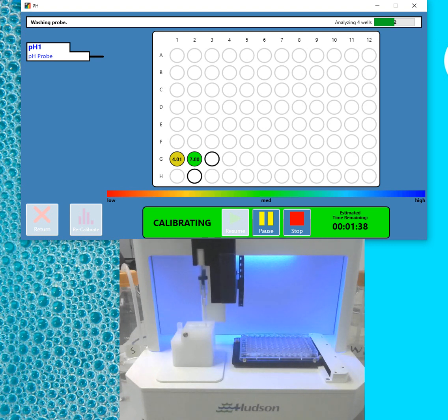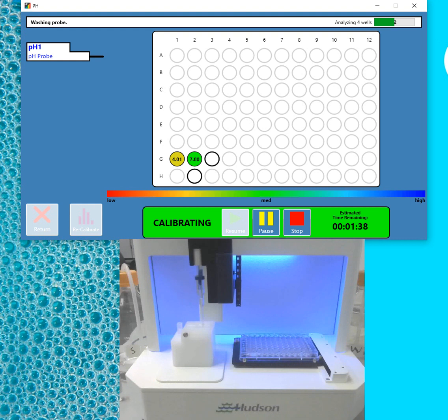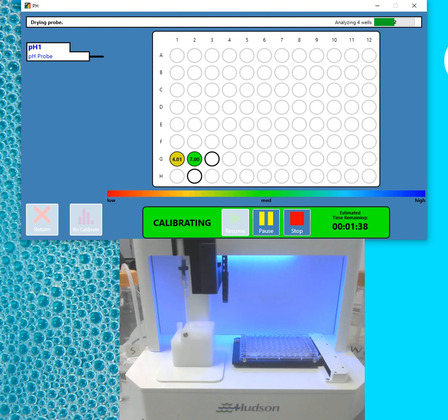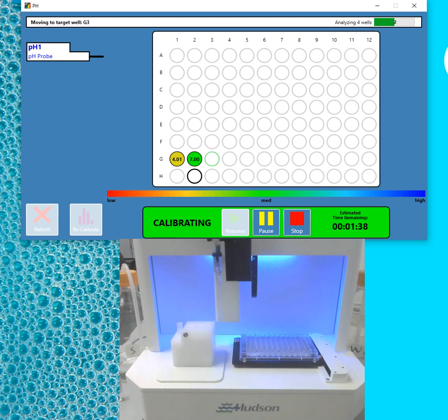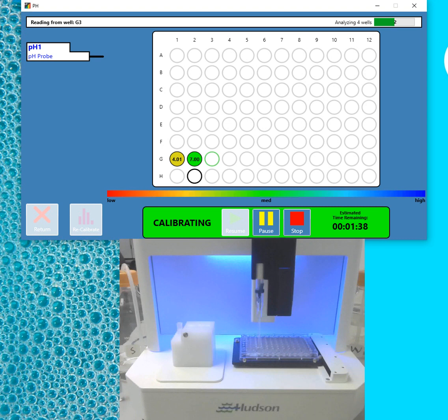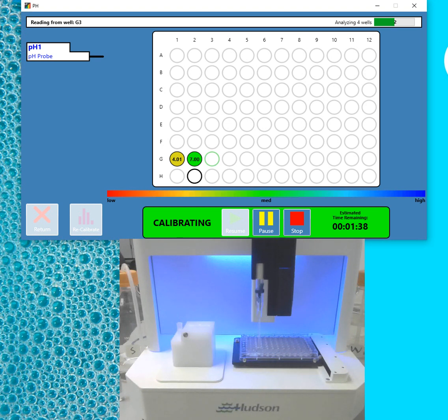So while this is running through the steps, I'll actually talk a little bit about what you can do when running a plate. After your calibration, you want to get started running plates and working on other things, you can either manually enter the descriptions into the wells. You don't need to add a description. Just by clicking on the wells you want to run, it'll highlight those wells, and then you hit start. You can also import data.